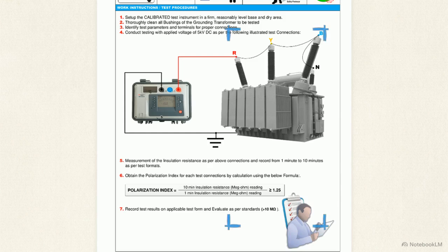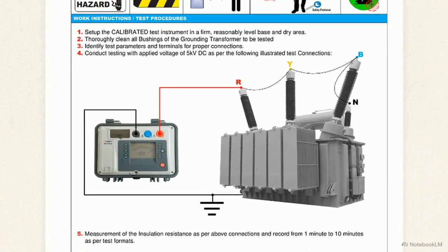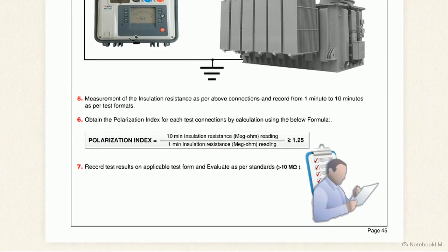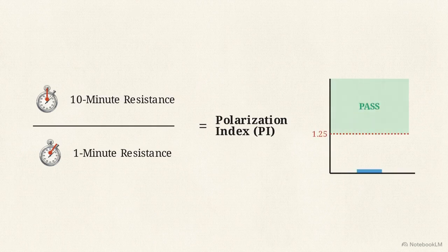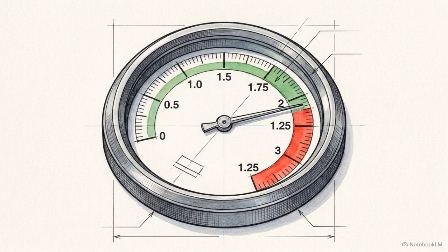The test instrument connects across the red, yellow, blue, and neutral terminals to push a regulated DC voltage into the windings. We apply the test voltage and monitor the leakage current, recording exact resistance values measured at the 1-minute and 10-minute marks to observe how the insulation absorbs the charge over time. These readings give us the polarization index, which is the ratio of the 10-minute measurement divided by the 1-minute measurement. The acceptance criteria demands a minimum index of 1.25. Anything lower requires immediate investigation.